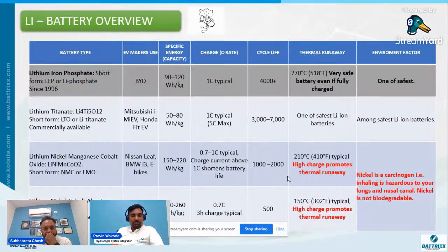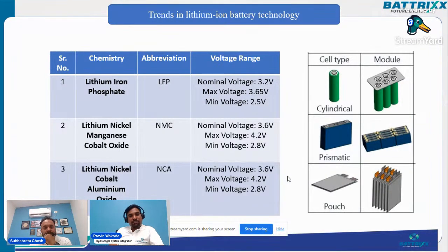Then nickel manganese cobalt, abbreviated as NMC. The nominal voltage for these cells is 3.6 volt. It can be charged up to 4.2 volt and discharged up to 2.8 volt. These are having more watt hour per kg than LFP, but it is not as stable as LFP. LFP is much more stable than NMC. And as compared to life cycle, NMC does not give that much life cycle, but LFP gives more number of cycles for any particular application.